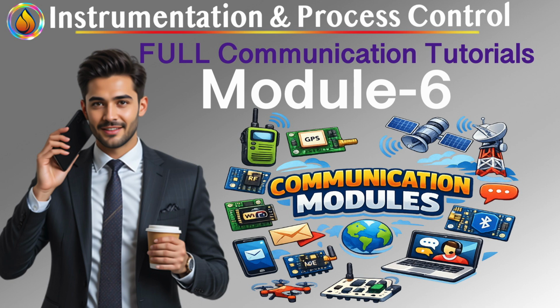Diagnostics, the quiet superpower. This is the part many people underestimate. Fieldbus doesn't just move process values, it moves context. Devices can report internal faults, sensor degradation, electronics temperature, communication quality. This turns maintenance from reactive to predictive. Instead of "the loop is dead," you get "the sensor is drifting, the actuator is nearing failure, the device lost synchronization." That's a completely different maintenance philosophy.